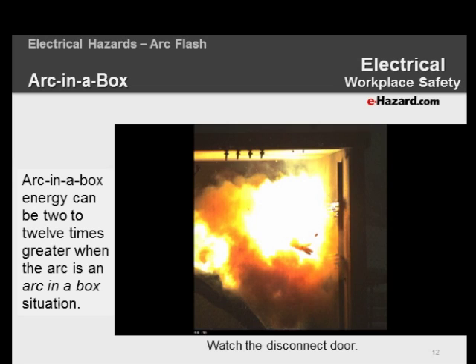Standing to the side, you see the hot gas of the fireball. Some of that's going to hit you, mainly on your arm and hand. We have companies that go in wearing cut-resistant sleeves that are also arc-rated, with a leather or cut-resistant arc-rated glove, and operate this equipment from the side while wearing just a cotton T-shirt.